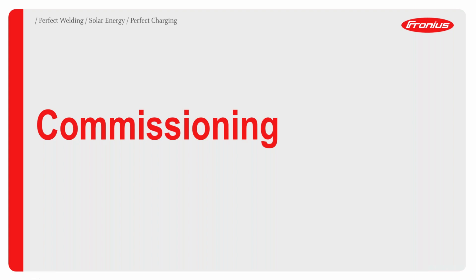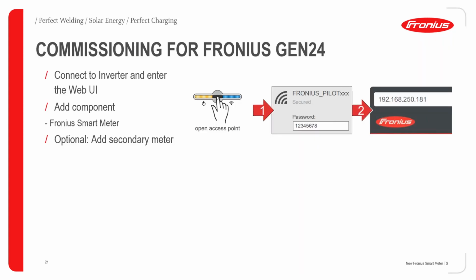Then commissioning. Of course, connecting the smart meter is one part, and the second part is commissioning. You have to tell the system there is a smart meter connected to it. So you have to reach the inverter's interface page. If it is the Gen 24 device, you can activate it. Since you do not have a display in the Gen 24, you simply touch the center button one time, then you will be opening the access point. Connect your smart device, it can be a laptop or mobile phone, to this inverter's Wi-Fi, and then you can go to the page.